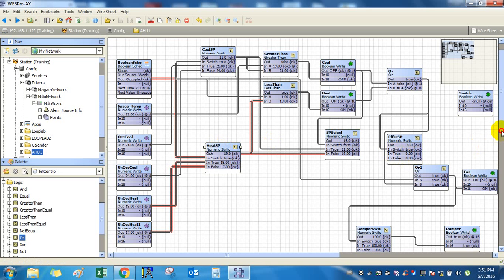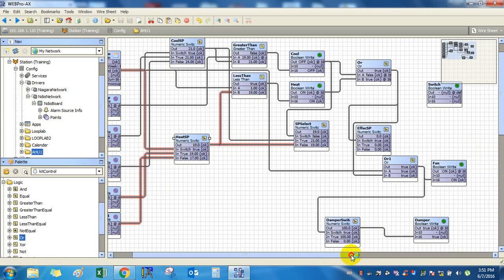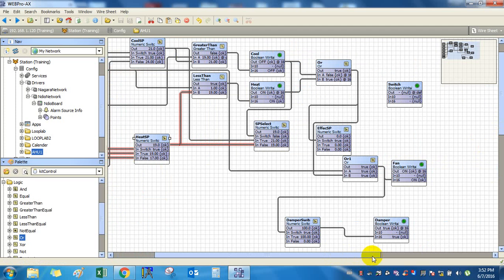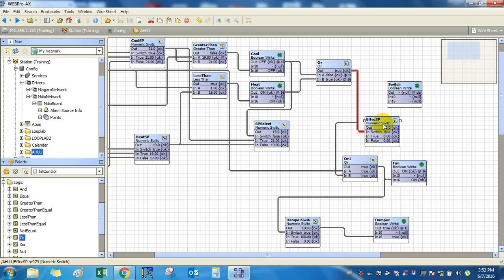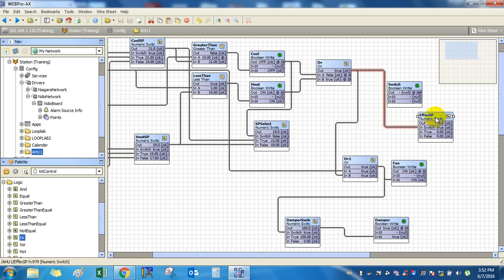Right? I had 4 here. By switching, I got 2. I still need only 1. So here, I decide which one of the 2. So if it is cooling, I go to the cooling set point. If it's not cooling, I still use the heating set point. But if heating is not enabled here, this set point is just one set point which is selected. The heating will not start. Right?